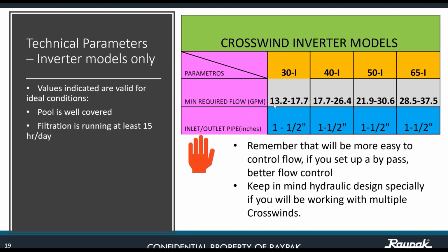Minimum required flow is 13.2 to 17.7 on the 30,000 BTU, 17.7 to 26.4 on the 40,000 BTU, 21.9 to 30.6 max on the 50,000 BTU, and 28.5 to 37.5 on the 65,000 BTU. Inlet and outlet for all the units is going to be 1.5 inch. Remember that it will be easier to control the flow if you set up a bypass. Keep in mind the hydraulics design, especially if you're going to be working with multiple Crosswinds.